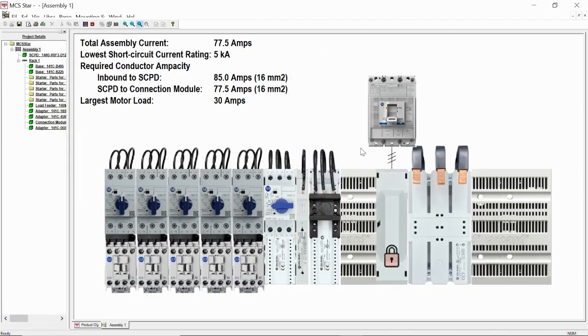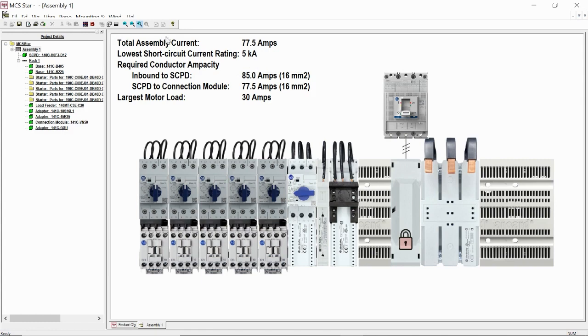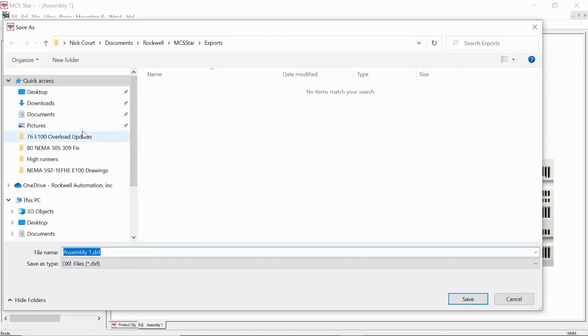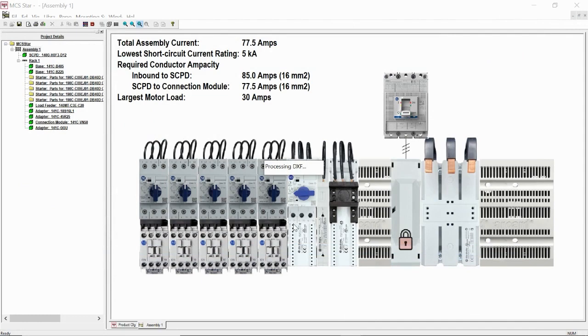This is going to bring our project back to a familiar environment for MCS star. You'll see it started to build a bill of materials for us. You've got our total assembly current here, our lowest short circuit rating. We can kind of find the weakest link and manage that. The other cool feature is this will actually give you a 2D drawing, a 2D panel drawing in DXF format. If I go to mounting system and click export DXF, you can save this drawing right off and pull that right into your drawing set. That's a nice feature to have here.